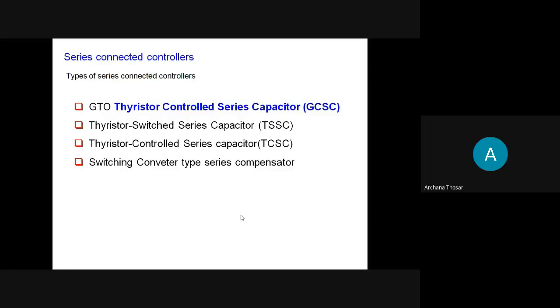But it doesn't mean that for every solution or every challenge you should go for a STATCOM. It might happen that for some problems, the other SVCs also can work, because whenever we give any solution for a power system, it should be economically viable also. So sometimes a very simple system, which can work with a fixed capacitor or TCR kind of thing, is sufficient, because the reactive power generation requirement is fixed for some period.